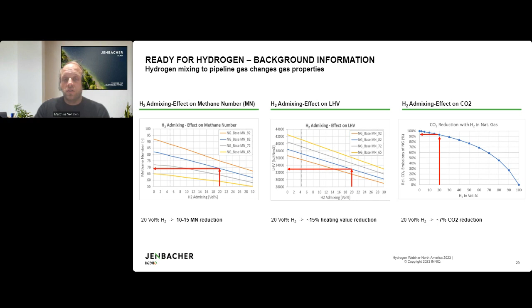If you upgrade or install a new engine running on up to 20 or 25% H2, you need to make sure the volumetric flow rate can be handled by the gas train. Now looking at the CO2 reduction potential as we add H2 to natural gas as a base fuel, across the whole range from 0 to 100%, it's worth noting this is not a linear relationship. 20% addition of H2 on a volumetric basis is not a 20% CO2 reduction - it enables about 7 to 8% CO2 reduction at 20 to 25% H2 added to the natural gas. So admixing technology is a first appropriate step in CO2 reduction, but to really reduce CO2 emissions from our gas gensets, we need to strive for high concentrations of hydrogen, ideally 100%, because then we've eliminated all the carbon in the fuel and won't see any CO2 emissions in the exhaust.